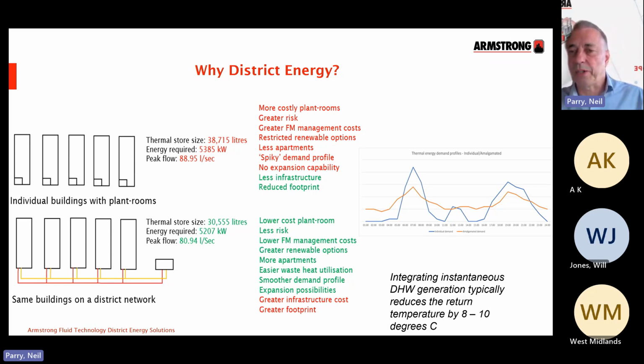I've also listed out what that equates to in terms of the text in red and green. I'm not going to read through those, but if it's red, obviously it's a negative, and if it's in green, it's a positive. So looking over at the graph on the right hand side, what you can see there is the resultant demand profile because of the aggregation of the loads. So the blue line shows you what an individual demand profile would look like, very high peaks and then times of zero demand. And as you add more and more apartments or more buildings, etc., onto the energy center, you find that the peaks and troughs tend to get smoothed out.